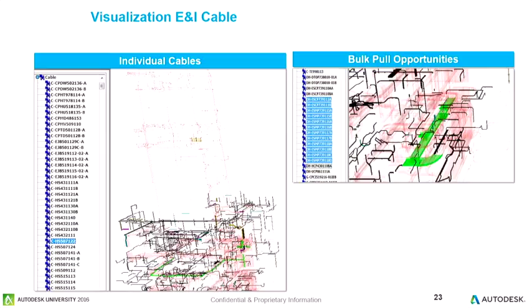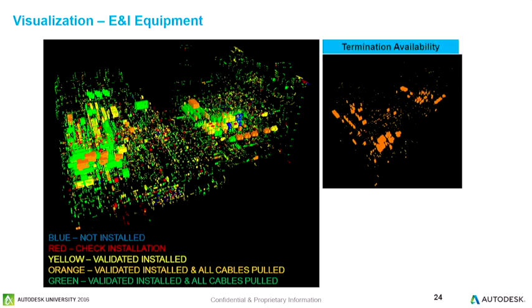So we could see the status of all of these end devices. What we were really trying to do here was drive through to open up termination availability, particularly in panels that had large volumes of cable. You want to get in, gland and terminate once, preserving the cabinet so you don't have issues as you get into commissioning.